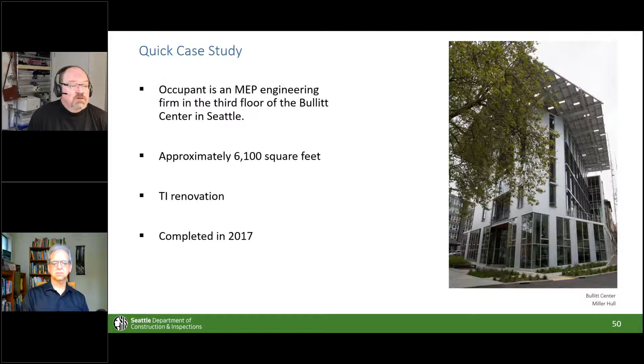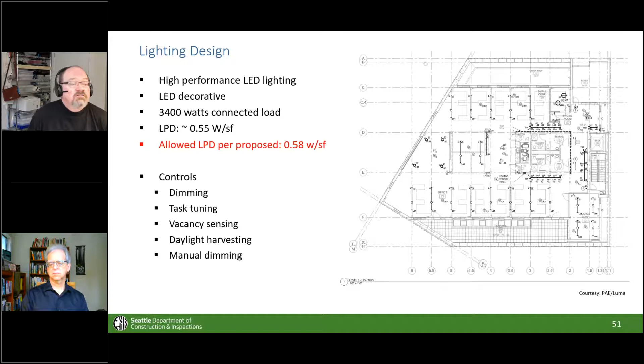So, we put this relatively high performance lighting design together. 2017, our power density was 0.55 watts per square foot. That's actually a little bit artificially high, in fact, because I intentionally overlighted the open areas there with the linear LED with the idea that I wanted to intentionally task tune down by about 30%, so that I could increase the lifespan of the LED lighting system that we had in there. Right now, today, the LPD proposal is 0.58 watts per square foot. We'd also designed in all of these controls that we would normally expect. Go to the next one.